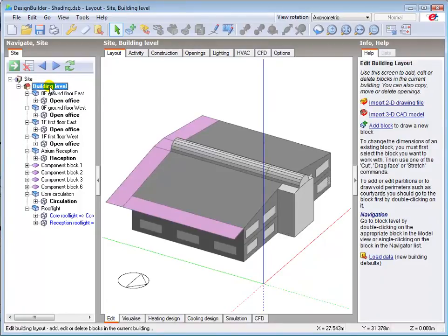Standard component blocks can be used to provide bespoke external shading as a feature of the building, such as the roof level shading applied in this model, or to represent adjacent objects such as buildings and trees which provide remote shading. When using component blocks as shading devices attached to the building fabric, you should ensure that the block is drawn on the external surface in such a way that it does not incorrectly shield the facade or roof from exposure to sunlight and ambient conditions.